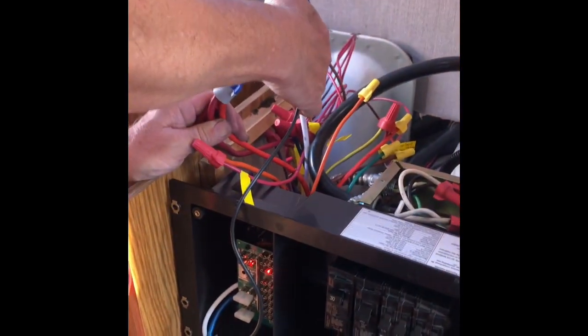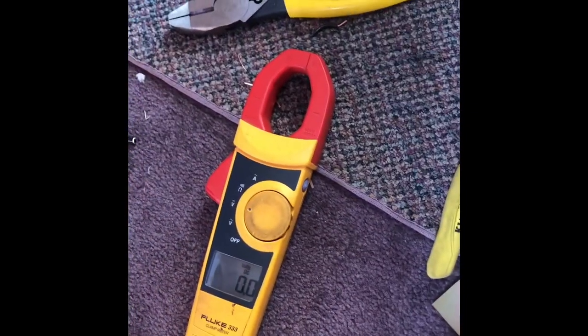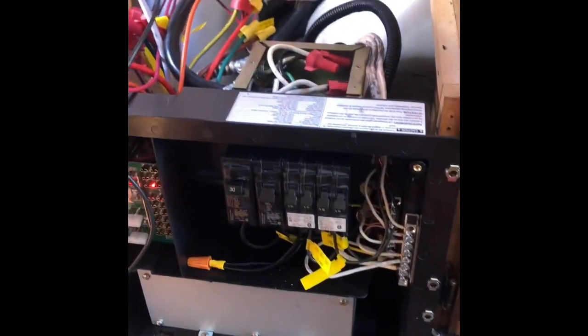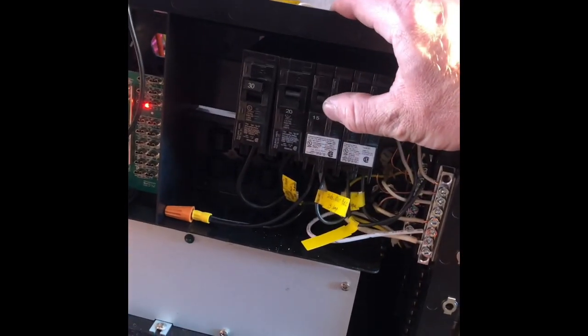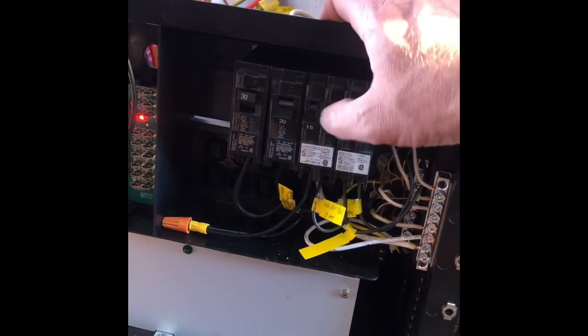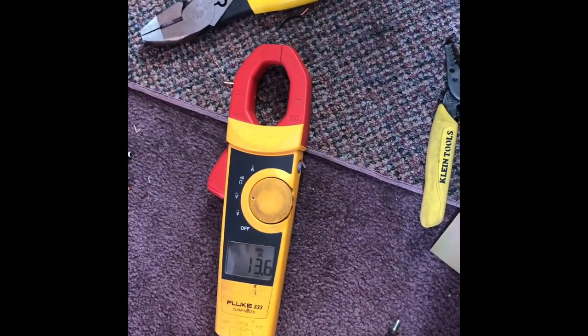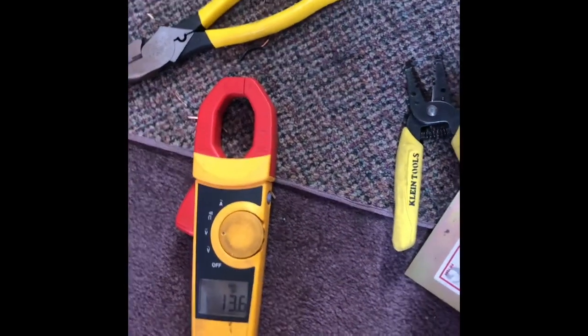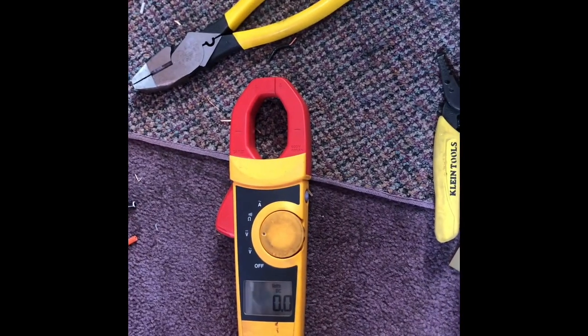Okay, we've got the leads of our multimeter on the positive and negative of the battery. Right now we're getting 0 on there, as we should be, because we've got our breaker off. I'm going to go ahead and turn the breaker on for the converter, and we should be getting... wrong breaker. Okay, you see the converter came on. 13.6 volts. That's good. 13.6 volts right there. The battery is charging. So that's good. Looks like we're good on the converter right now.